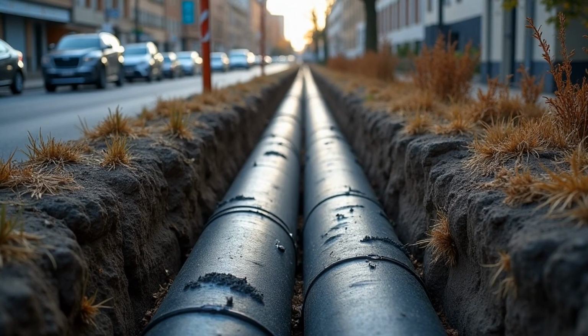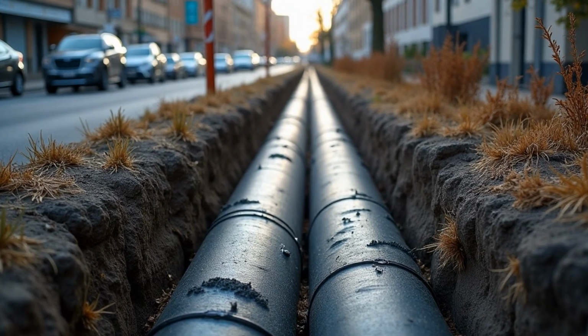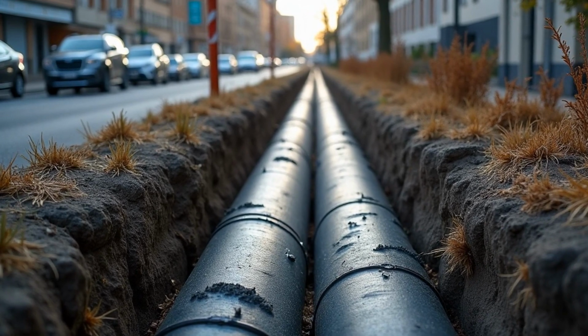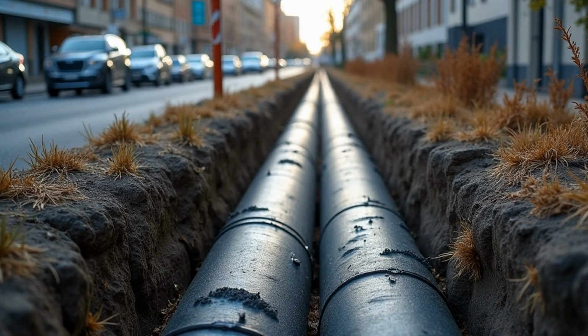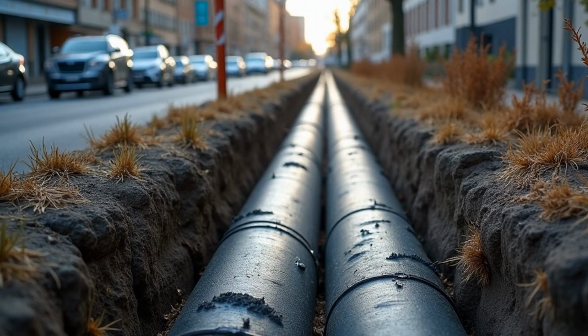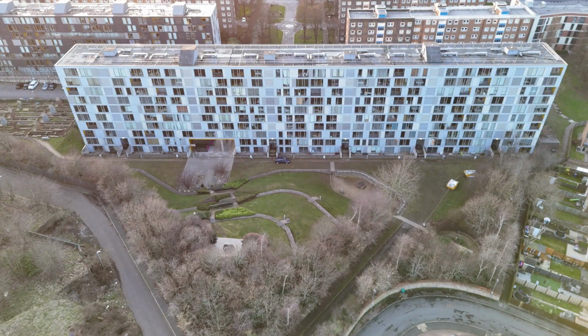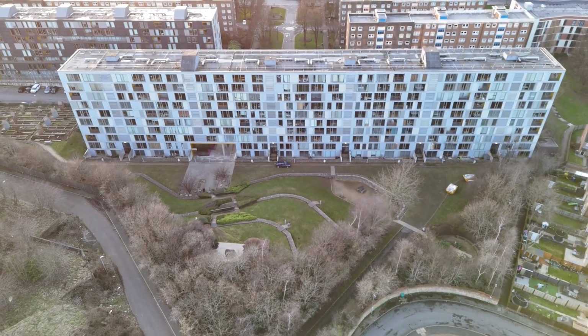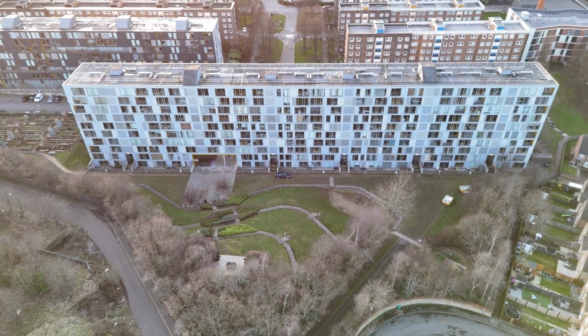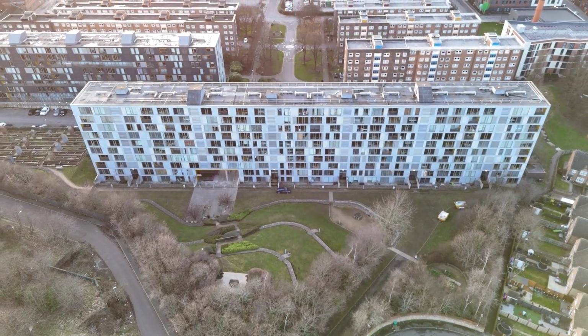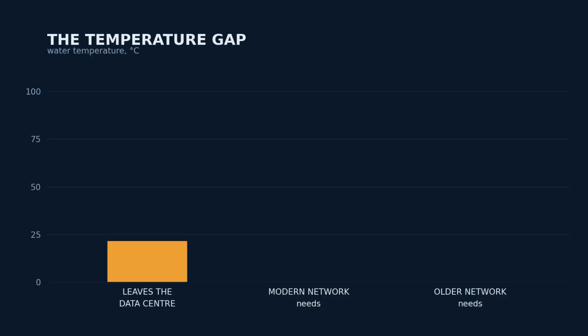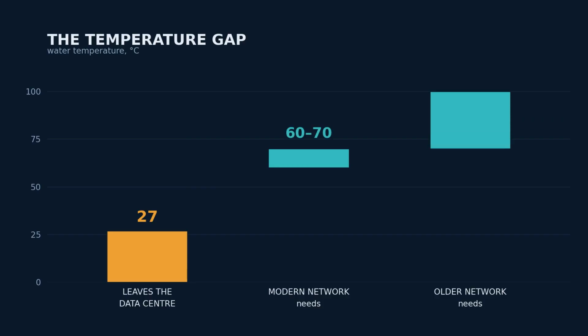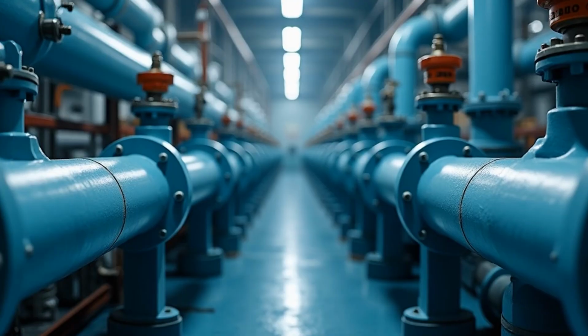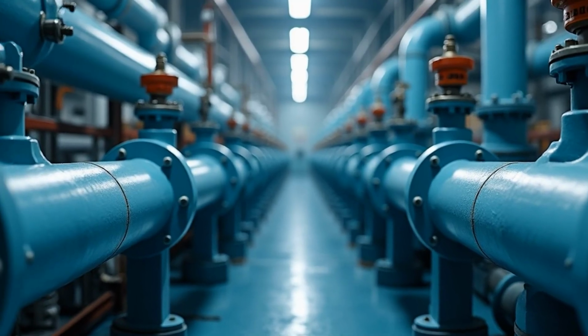Because of what a heat network requires at the other end. Modern district heating, the fourth generation kind, wants water at 60 to 70 degrees. The older networks, which is what most European cities actually have in the ground, want 70 to 100. So there is a gap between what leaves a data center and what a city will accept. Temperature gaps do not close by wishing. In Odense, they close it with hardware.